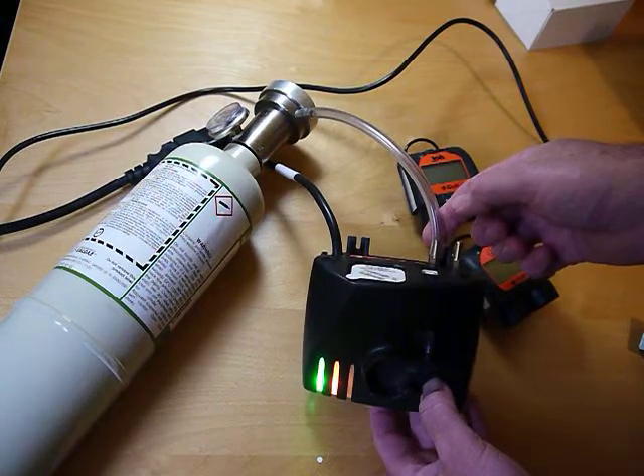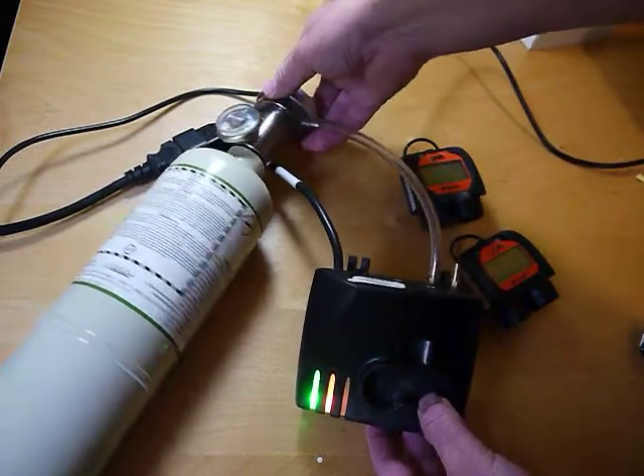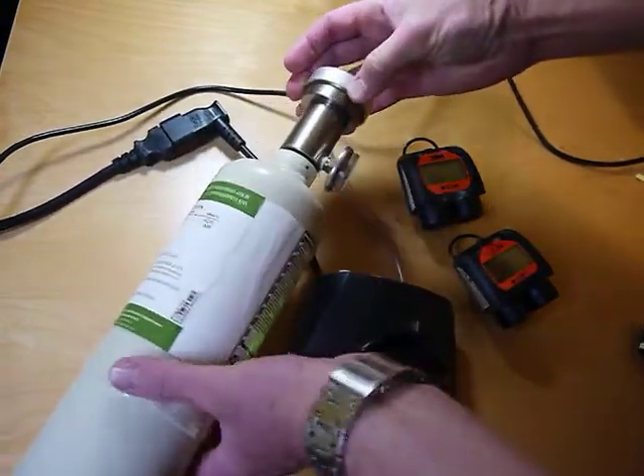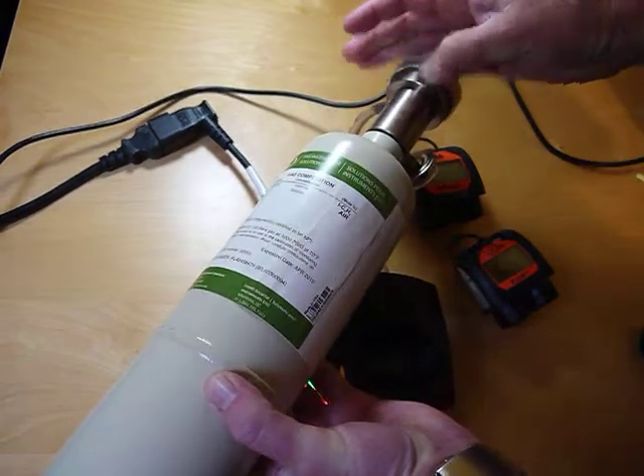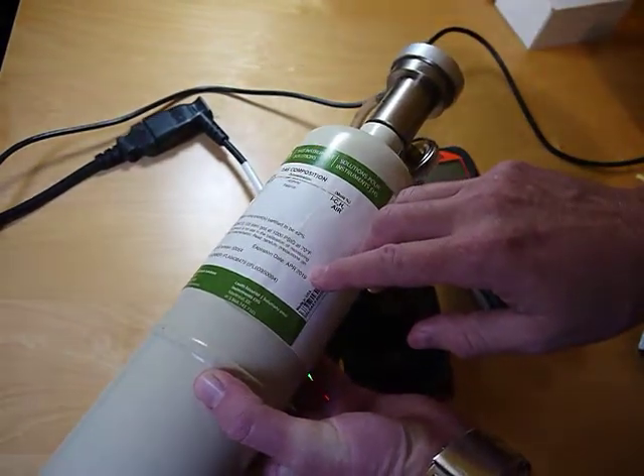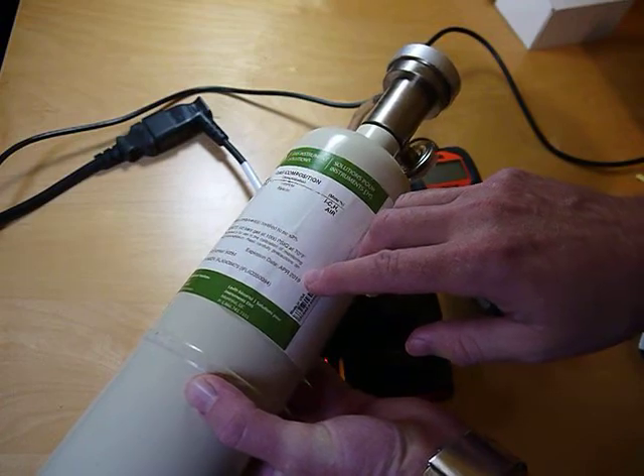Port 2 is for your calibration gas. In this case I've got a demand flow regulator hooked up to 100 ppm isobutylene gas, and I've got an expiry date of April 2019, so this gas is still good.